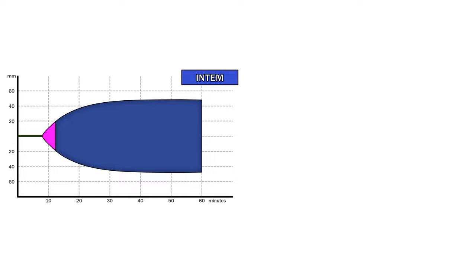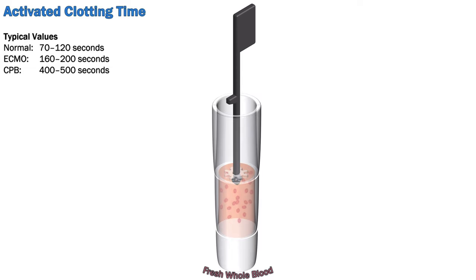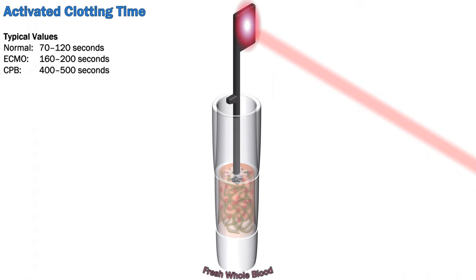If you were confident it was mostly just heparin effect, you might not need a full ROTEM — in that case a point-of-care APTT equivalent that you don't have to centrifuge would be sufficient. The activated clotting time is just that: a typically mechanical whole blood assay that assesses time to clot formation when stimulated by the contact pathway. One time the contact activation pathway is actually relevant is extracorporeal circulation, as it is the primary initiating factor for clot formation in that case. ACTs usually don't even use citrate — just whole blood. One example uses a plunger that passively falls through a blood sample sitting on a contact activator in a tube, lifted up regularly, and when viscosity increases enough to delay the fall it's detected by an attached flag with a laser. The ACT doesn't perfectly correlate with APTT, which tends to be about a third as long, as APTT also eliminates the platelet effect.